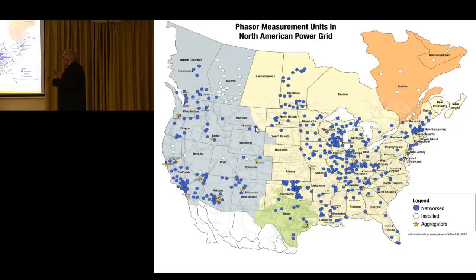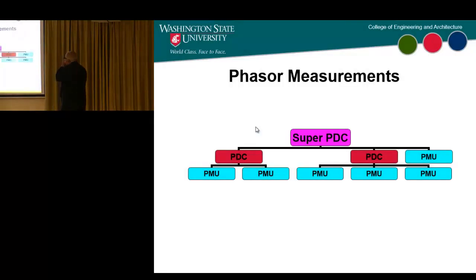But the reason we don't have more, as I'll tell you in a bit, is we're not sure what we can do with them—that's the big issue. The other problem is whether the data is coming in fast enough that you can actually do relay-type or control-type applications with this rate of data. Relays operate in a few cycles, so you're talking milliseconds, tens or hundreds of milliseconds, to do control. You could never do that with the old SCADA AGC system because the data rates were much, much lower.